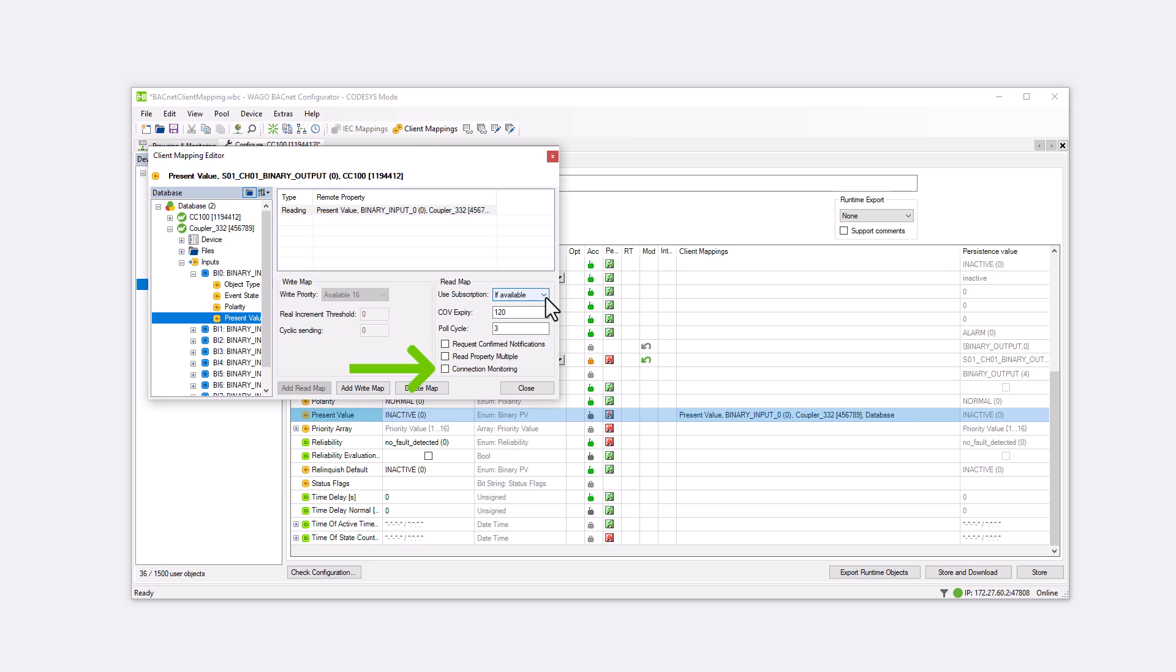Connection Monitoring: Connection Monitoring is a cyclic monitoring function for a connection between BACnet objects and devices. When enabled, the BACnet device monitors the status of client mapping connections by cyclically querying the properties status, time of device restart and database revision from the server's device object. The query occurs every 60 seconds. Monitoring allows timely signaling of a connection interruption before a polling interval has elapsed or a COV subscription renewal is needed.